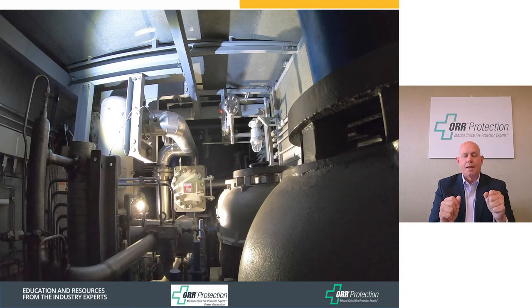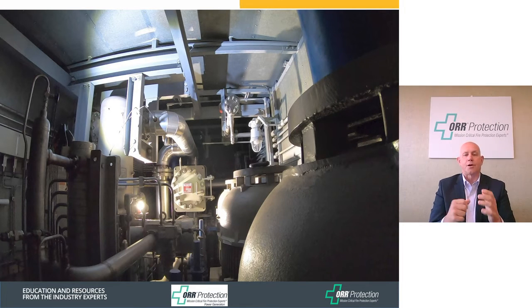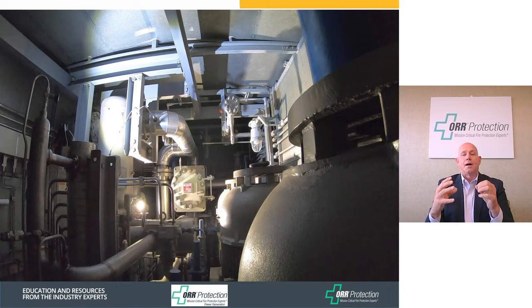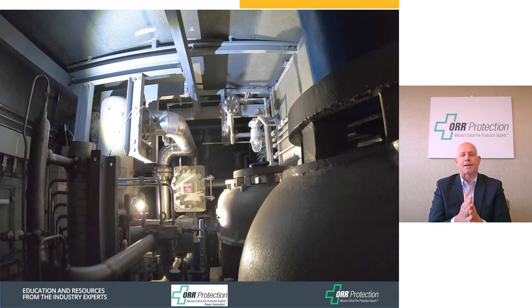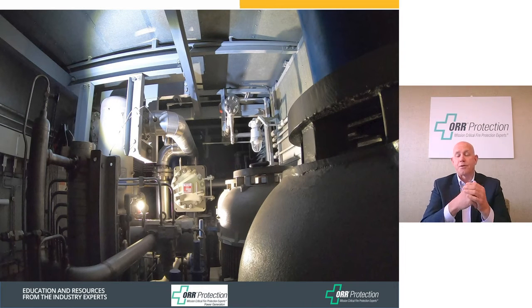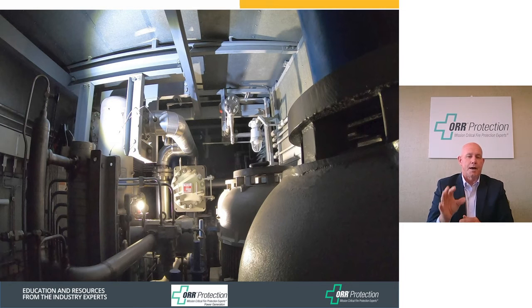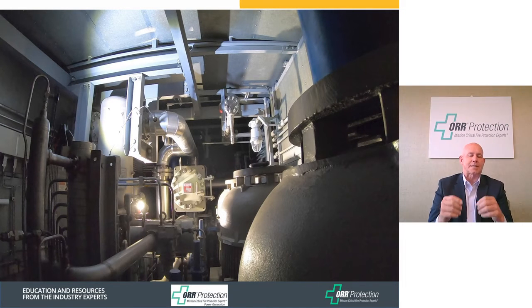Now we're going to show you a complete CO2 discharge. During this discharge sequence, you'll see the electronic audibles, the strobe in the background, and hear the pneumatic siren — all part of NFPA 12. Then you'll hear the discharge and see CO2 coming out of a nozzle and watch the entire cycle. Many people who have had CO2-protected zones for many years have never actually seen a CO2 discharge in video or real life, so this is really impactful.